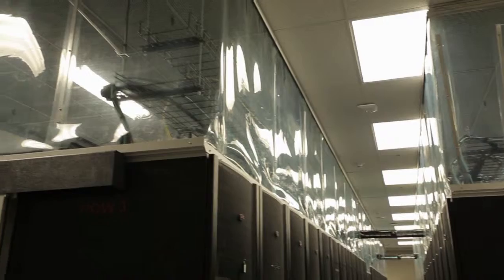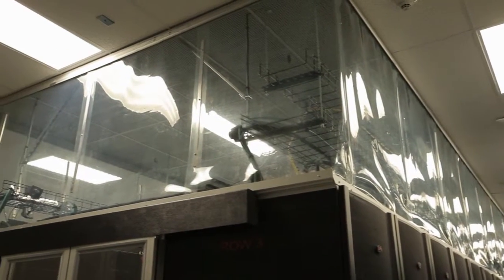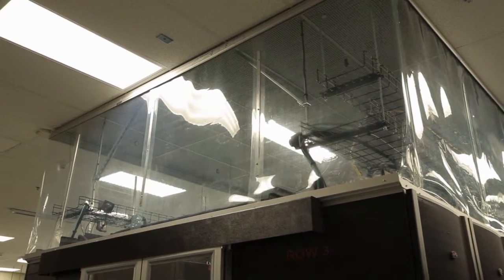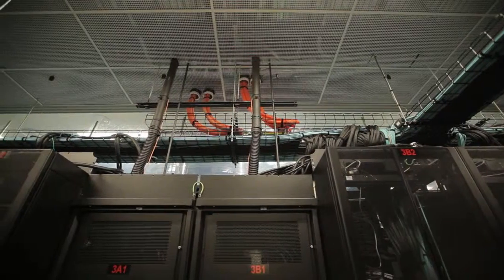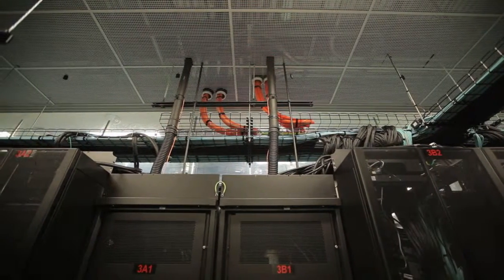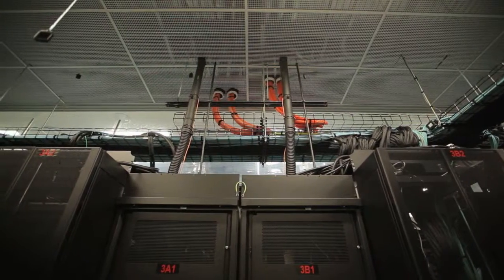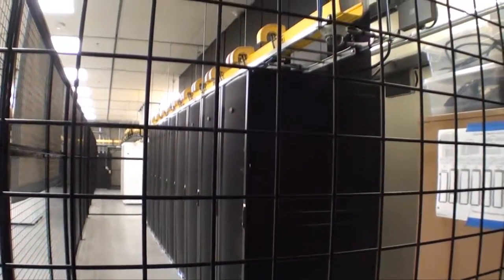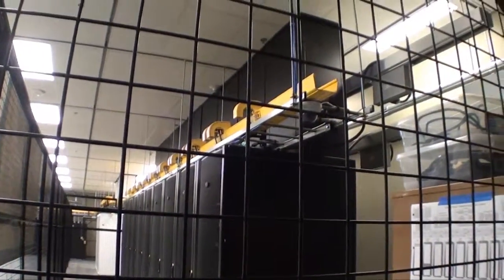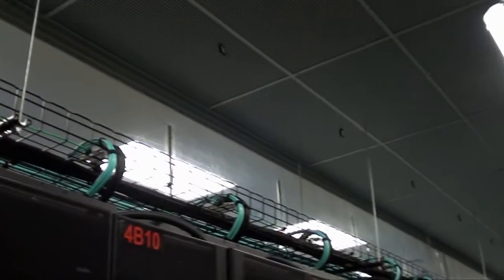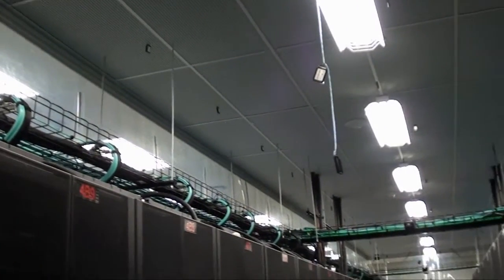What that does is that eliminates the mixing of the cold supply air with the warm air that's coming out of the back of the servers. Instead of that mixing occurring, that warm air goes directly into a ceiling plenum and then to the air handler equipment. So we require hot aisle containment for our wholesale colocation customers. We've used different kinds of pods, we've used different kinds of cabinets, different kinds of chimneys. We're very flexible there, but we always use some form of hot aisle containment because it's just the right thing to do. We believe it's the most cost-effective way of cooling the data center overall.